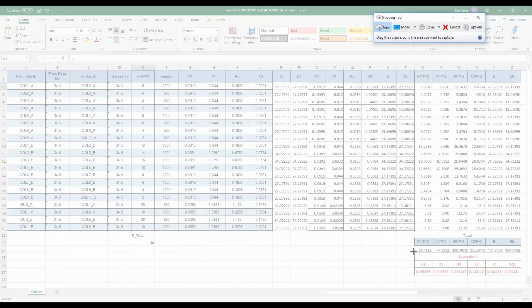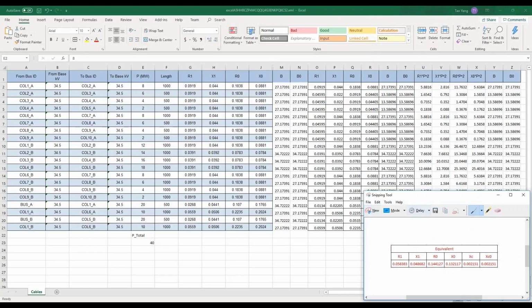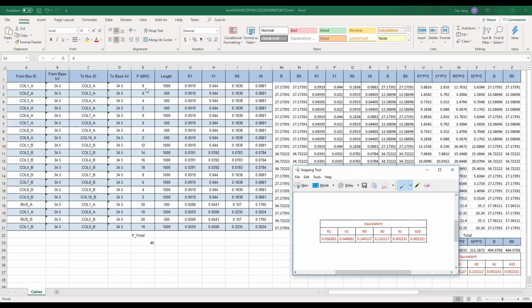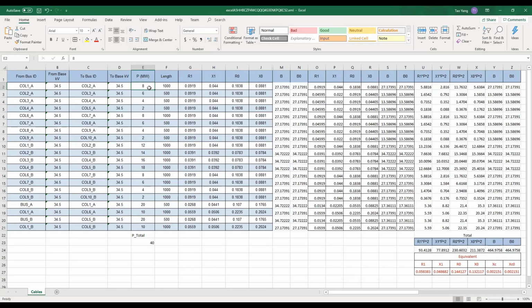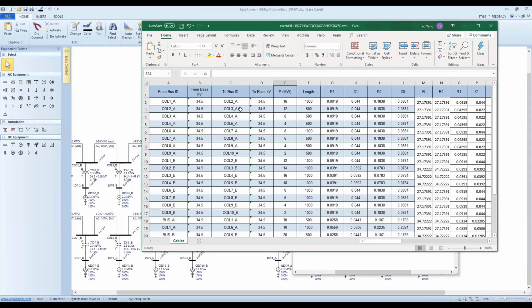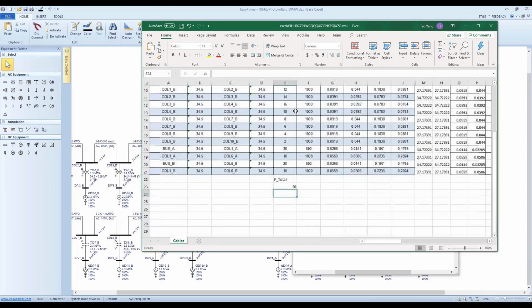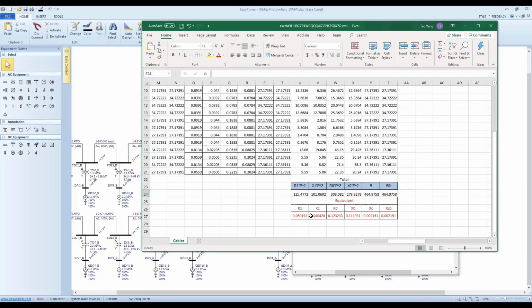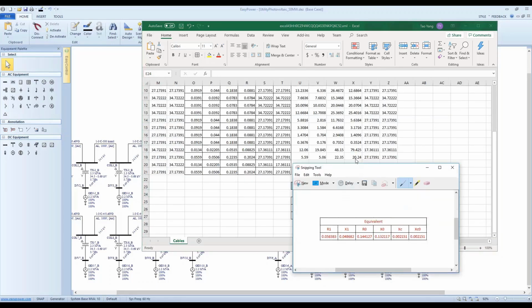Now you can see the difference here. Let's take a snapshot of what's before. This is our 40 megawatt equivalence, right? So let's just change the megawatt and see what has changed. So you got a 16 here, 12 here, 8, 4, and eventually you have 30 megawatt and you have 50 megawatt in total, right? Because anything related to collector 1A and the upstream needs to be doubled because you use 4 megawatt, and P total needs to be changed to 50. Now this number is for the 50 megawatt design, which is different.